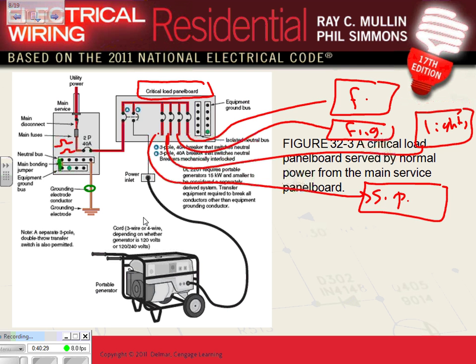The second thing you add is close to 40 or 60 amps, commonly 40 or 60 amps. Here's a 40 amp. You bring a feeder, 40 amp, number 8 conductor, all the way to another sub panel that could be in the garage or a basement, completely sub panel. Inside the sub panel, it comes designed with these two circuit breakers. These are the single most important thing, guys, right in here. The single most important thing about the whole system. Safety. If you have a generator, they want you to have two circuit breakers that mechanically interlock. This is how they work, mechanically interlock. If you turn the generator circuit breaker on, it's connected, the utility with the same movement will be off. If you turn the utility on, the circuit breaker for the generator will be off.